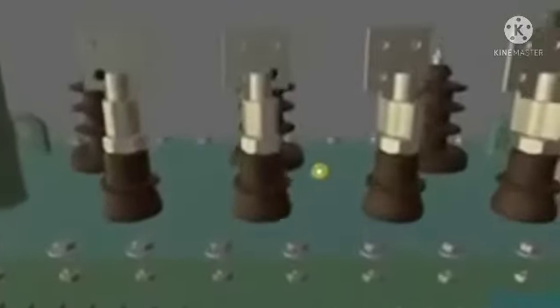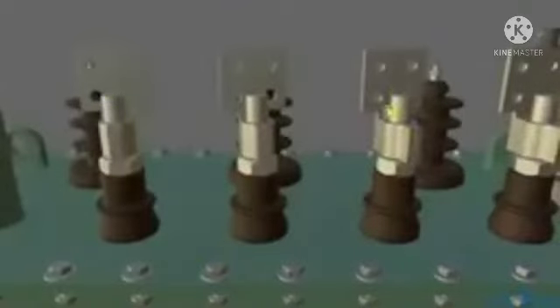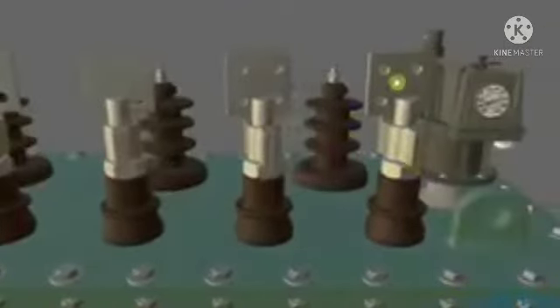We can see on the top that we've got some low voltage bushings. That's these 4 thick ones here. The reason you can tell they are the low voltage bushings is because the connections are very large. The reason they're large is because the voltage is low and the current is high. So that's a giveaway that the low voltage bushings are these 4 here.